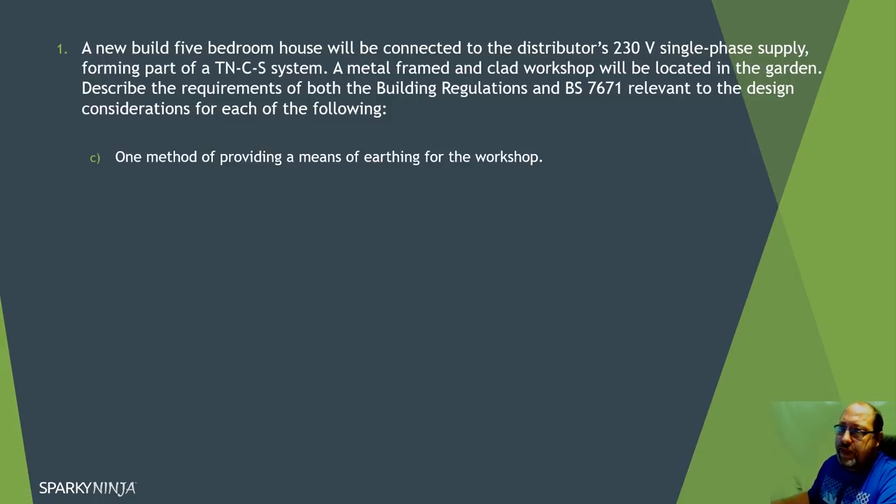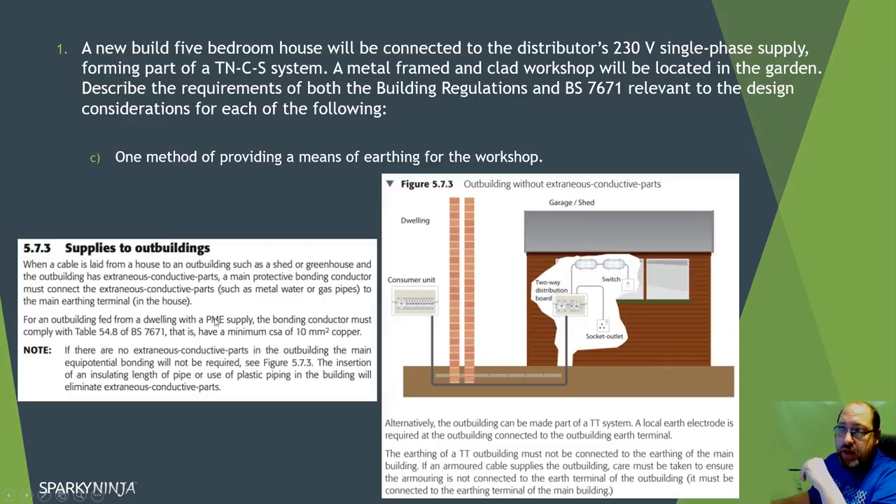For one method of providing earthing for the workshop, the key thing is the metal-framed and clad workshop - the metal frame means the workshop has become an extraneous conductive part because it's in contact with the earth. So the question of whether it needs to be bonded - yes it does. In the building regulations book, if you look up sheds and outbuildings, it will tell you that with an external PME supply and extraneous conductive parts, we either take our protective bonding to the extraneous conductive part or create a separate TT system.